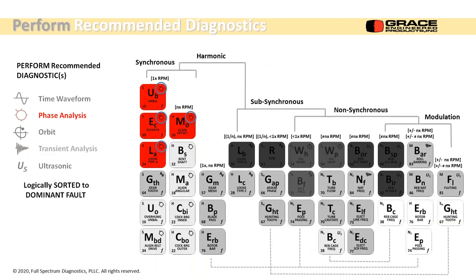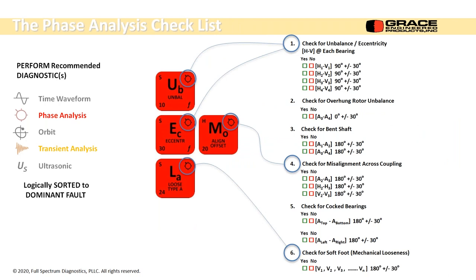So what's left? These 4 phase diagnostics for unbalance, eccentricity, looseness type A, and alignment offset in the radial direction. What are those tests? These are the categories. So doing the phase test, not really important right now. Understanding it, what it gets you is very important. So I check for unbalance and eccentricity. I should have a horizontal to vertical phase shift of 90 degrees at each bearing. So all I do is check the boxes for those that apply.